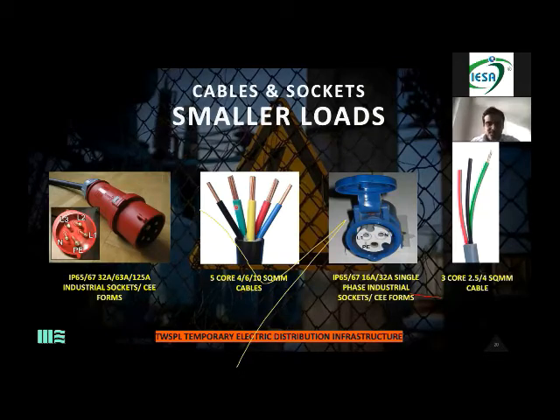So now what is happening? As soon as you start distributing the power, let it be to your exhibitors, you have an exhibition going on. The panel is there, the panel already has a socket, so you're laying your cables and giving the power to your exhibitor or anywhere. Automatically, the earth reaches the endpoint. In a normal case, we were using only 4 cores, people were using only black, yellow, blue, and red, and not this green wire. What is happening? They are compromising on the safety factor, because only these 4 wires are required for your electricity to be on, but this 5th wire is for the safety factor. It is for saving your life on site, so nobody wants to buy it. But as soon as you shift to the socket system, your earthing goes from the first point till the end point. So these are for the 3 phase.